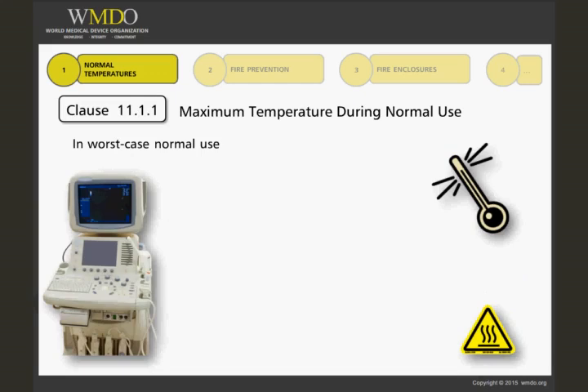When running the temperature test on medical electrical equipment, it is operated in the worst-case normal use, including the maximum ambient operating temperatures, which are specified in the user manual. It can also be run at normal laboratory ambient, and the resulting temperatures are corrected for the specified maximum ambient. The equipment parts shall not reach temperatures exceeding the values given in Table 22 and Table 23 on the next slide.